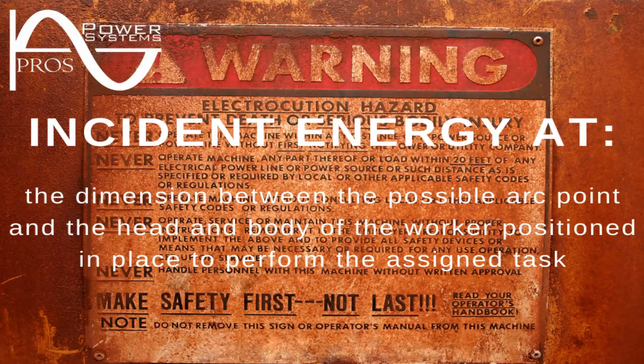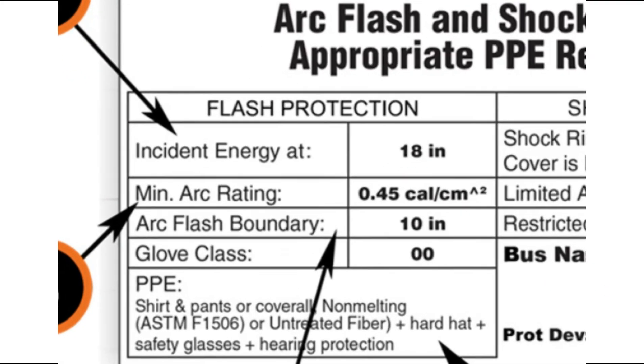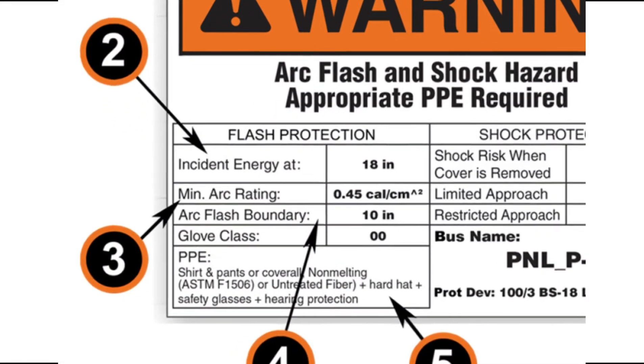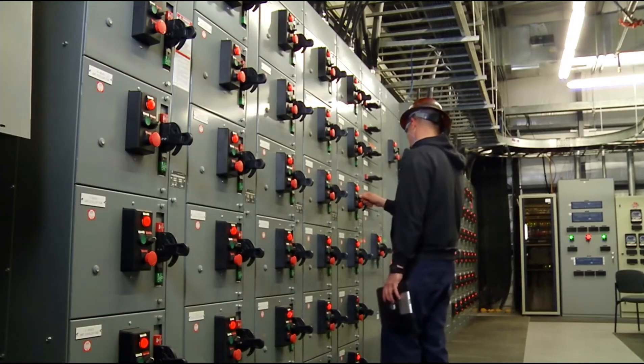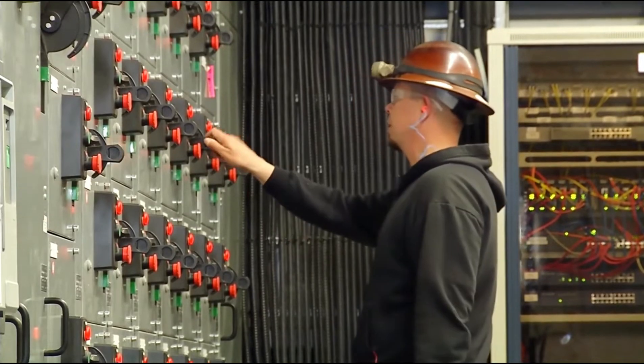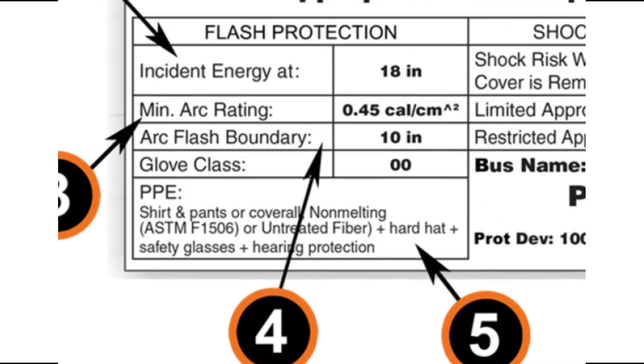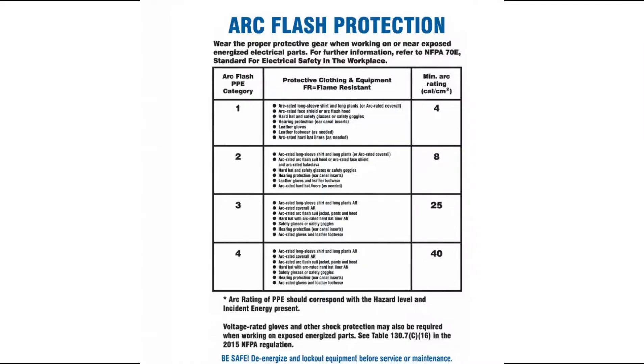Number two: incident energy at the corresponding working distance. The IEEE defines working distance as the dimension between the possible arc point and the head and body of the worker positioned to perform the assigned task. Number three: minimum arc rating is a measurement in calories per centimeter squared or joules per centimeter squared of thermal energy at a working distance from an arc fault. Number four: the arc flash boundary — the shortest distance at which a person may receive permanent injury, which is the onset of a second degree burn or worse, if not properly protected by arc-resistant or flame-resistant clothing or PPE. Each hazard risk category requires a different level of protection; categories range from one to four. Category zero was removed in the NFPA 70E 2015 edition.